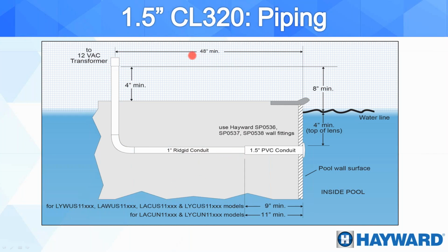Remember that we need a minimum of 48 inches between any type of electrical connection and the perimeter of our pool. So with that other type of junction box, the white one that goes on the deck, normally that will be right here. But remember, we don't want to do that because that doesn't meet any kind of safety code. The safety code says that you have to be 48 inches or more away from the perimeter of the pool. So this is why we're coming here with this conduit further away. And at the same time, any type of electrical connection is going to be above the water level, at least 8 inches. So we can see here, it will be our electrical connections. So it is farther away, and it is also higher than we would do with a standard junction box.